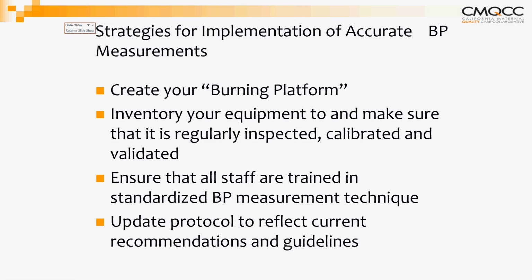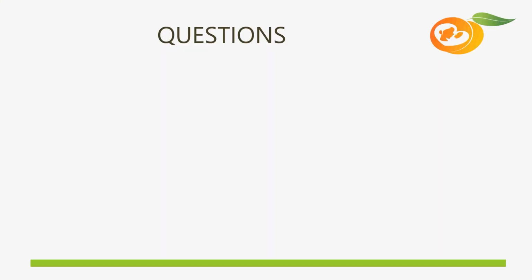Make sure that equipment is inventoried at a regular interval, at least annually, and that it's regularly inspected, working accurately and calibrated, and that staff are aware of the standardization of blood pressure measurements, and ensure that protocols are updated to reflect these recommendations and guidelines.